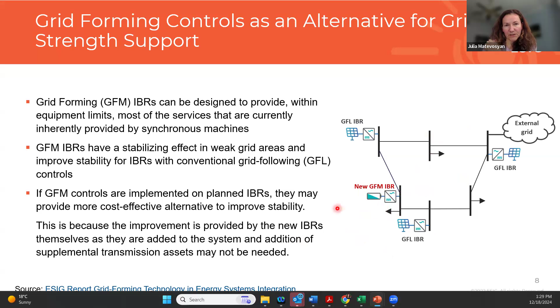But this is additional cost, right? You need to have a new transmission asset built, and this causes additional cost. If, on the other hand, this new resource that will be added anyway is added with grid forming controls instead of grid following, then even for contingency conditions this part of the grid can operate stably and you don't need a synchronous condenser here. So you can basically avoid additional transmission reinforcement by changing controls on the resource itself. And of course this saves costs because you are avoiding the new transmission assets.